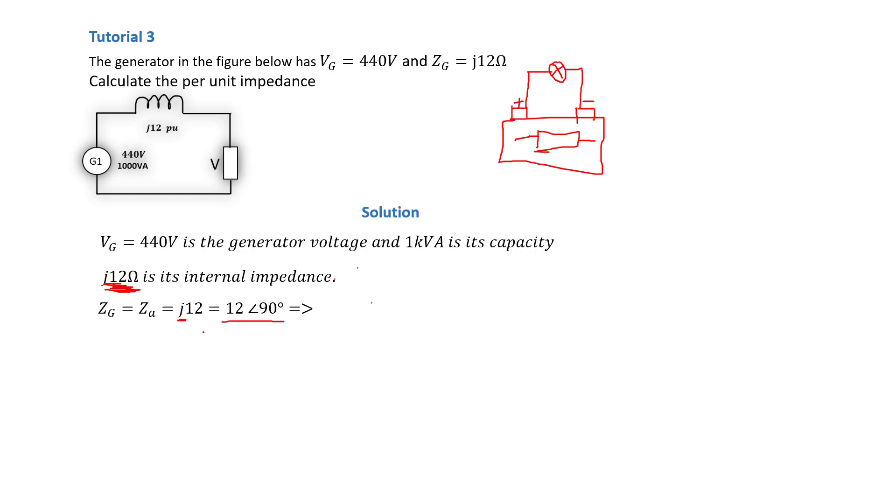Now that we know what the internal impedance of the generator is, or what we also call Z_actual, we can calculate Z_per unit. We can calculate the internal per unit impedance of the generator with the formula: Z_per unit internal equals Z_actual over Z_B. But what is Z_B? We've seen in the previous per unit tutorial that Z_B must be calculated with the base voltage of that zone squared and divided by the apparent power.